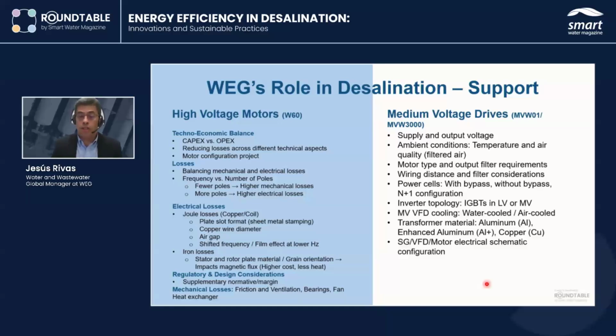The topologies, we have two topologies in the market, depending on the IGBTs. In the inverter, these small components in the power electronics are made in low voltage or medium voltage. For sure, we have to look to the cooling system, air cool, water cool, or even a hybrid system that we are developing now. And also the drives have the motors, have the transformers, with different materials, you have different efficiency. But the most important thing about this configuration is to look at the whole electrical schematic configuration, with the medium voltage switchgears that feed the drive, and in turn the motor. By looking at these voltages, powers, we can optimize the investment prices and efficiencies of each of these components, so that together they can give the highest efficiency at the best possible cost.